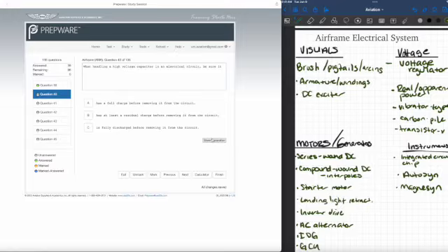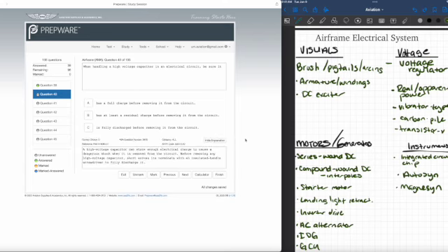So when handling a high voltage capacitor in an electrical circuit, be sure it is fully discharged before removing it from the circuit. A high voltage capacitor can store enough electrical charge to cause a dangerous shock when it is removed from the circuit. Before removing any high voltage capacitor, short across its terminals with an insulated handle screwdriver to fully discharge it.